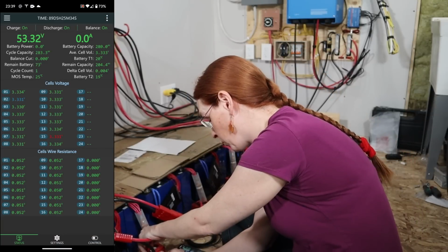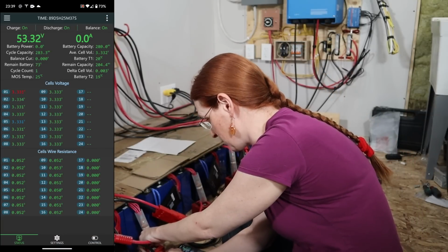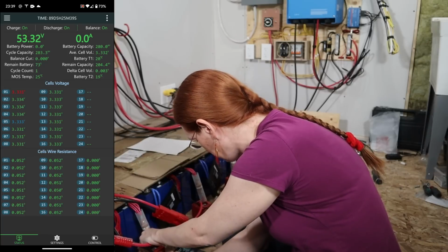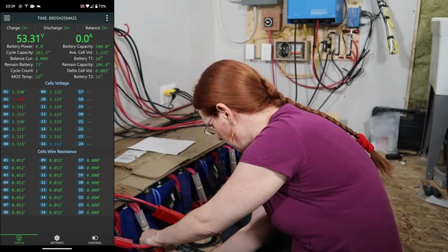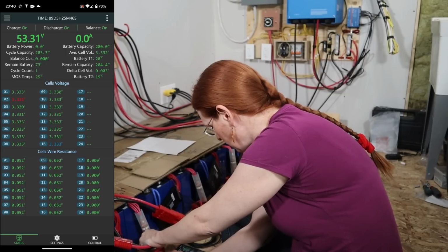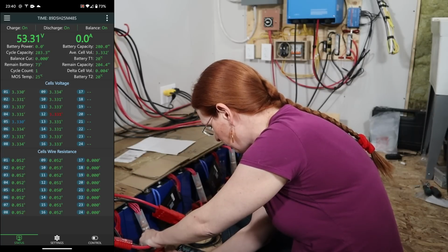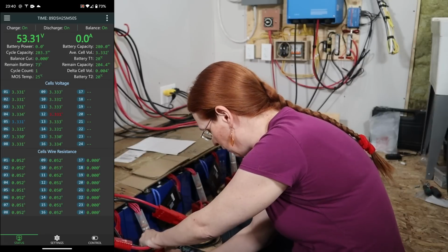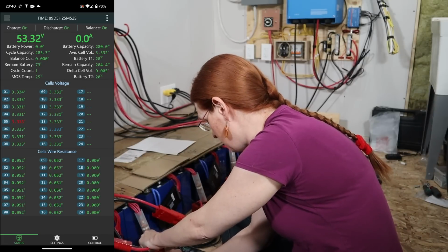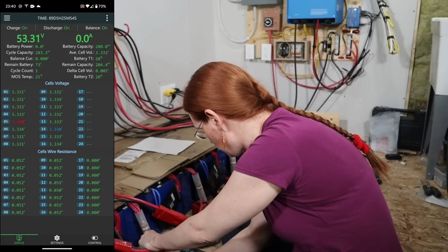It's saying 204 amp hours remaining capacity, which is going to be not even close to right. The delta is 0.003, average cell voltage is 3.3. So it would have been balancing along here, but it's not balancing because the delta voltage is too low.